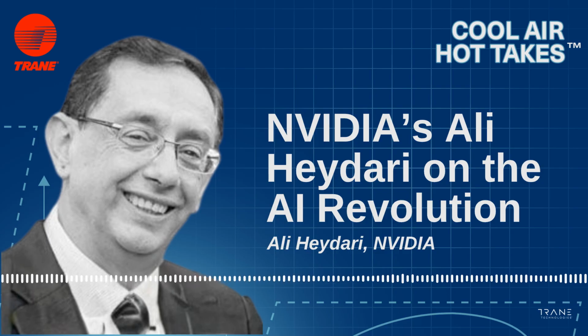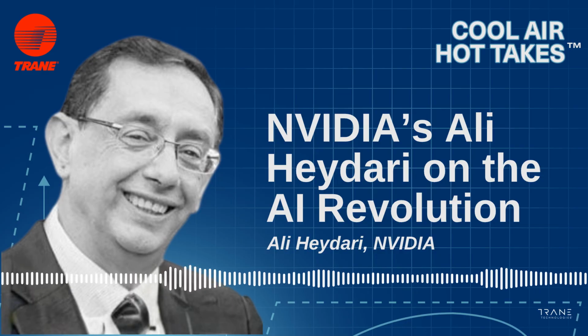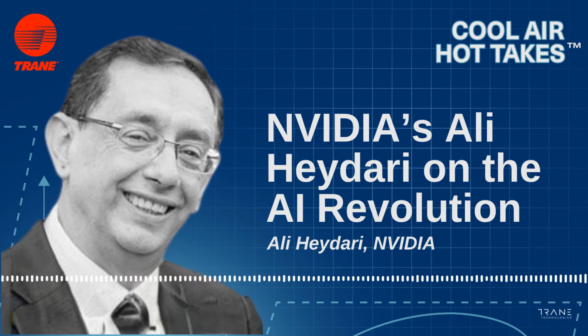Corrosion is one of the biggest issues in liquid cooling. PG25 was a concentration that kept the conductivity and thermal performance close to that of water, but brought a great deal of resiliency. We've been running with PG25 pretty successfully with very little issues since about 2020-2021.